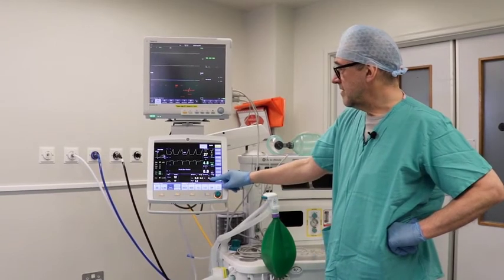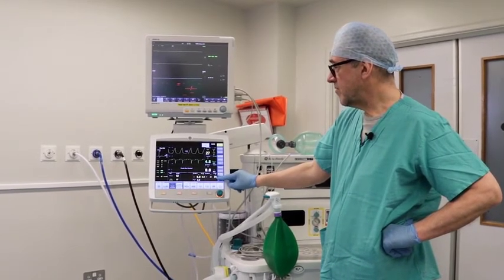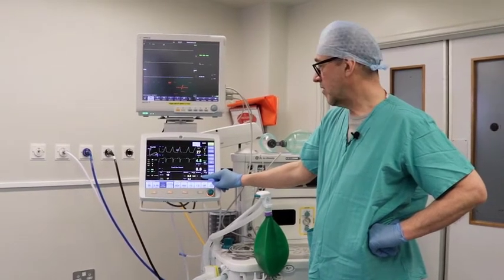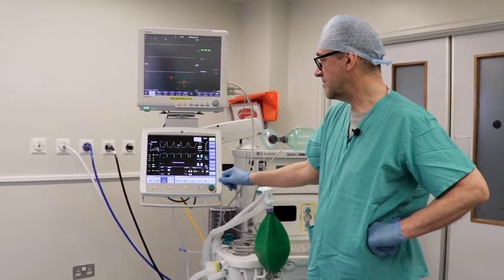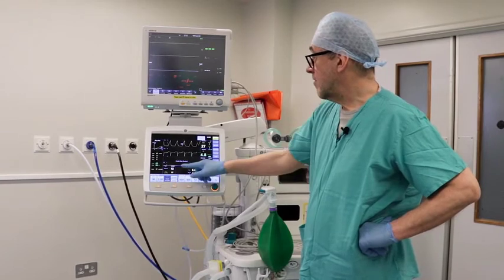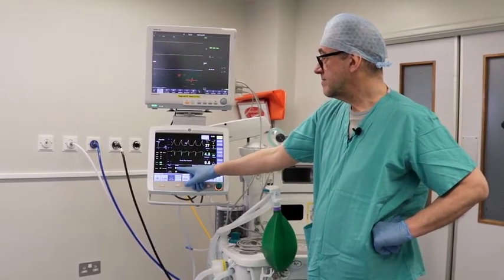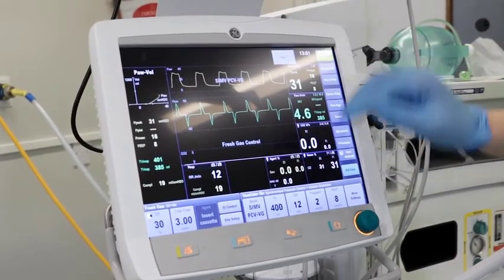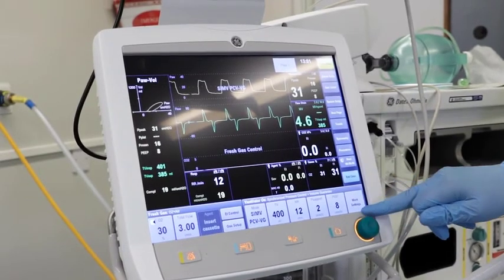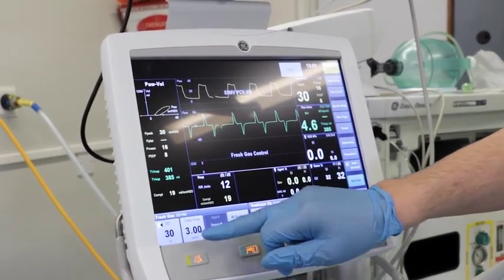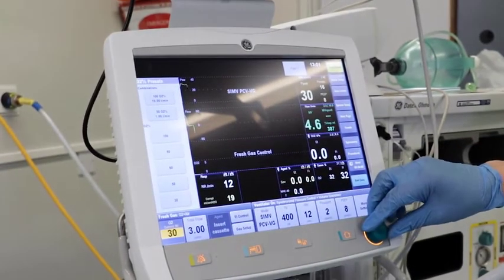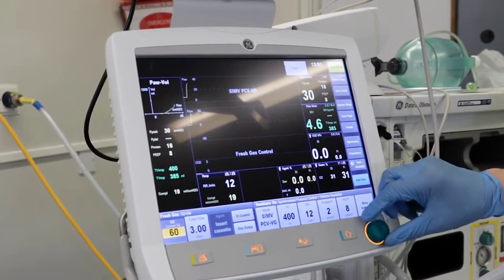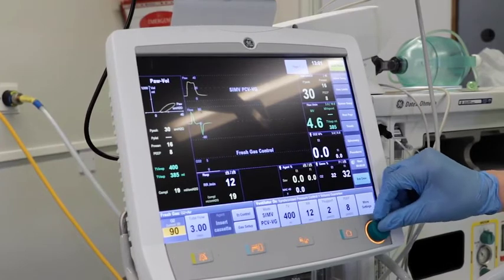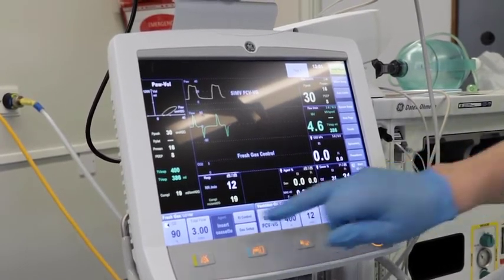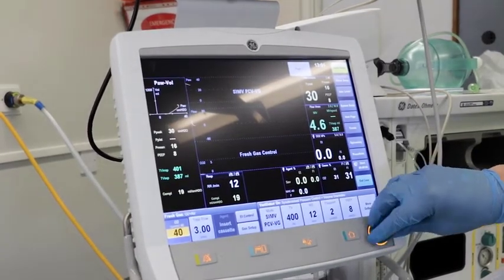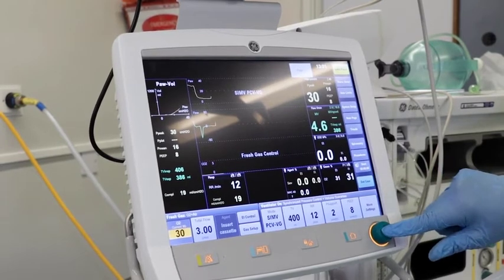Down here is the inspired oxygen value on the right and the expired oxygen value on the left, and it's currently set at 30%. Over here is the respiratory rate. So this is a touch screen, and the ventilator is operated by using the controls on this bar at the bottom. If you want to change something, you touch the screen, and using this toggle increase the value. When you reach the value that you want, press the toggle to set it. To reduce it again, touch the screen, turn down with the toggle. When you reach the value you want, press the toggle to set it.